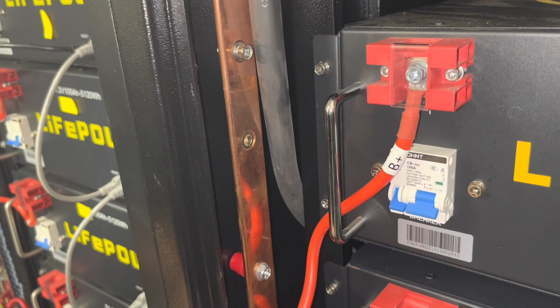All right, this is the older rack, and you see that lug. 100% surface area of this lug is on this bus bar, and that's really what you want for an electrical connection. So this design, in my mind, is far superior to that rivnut design that took out half the bus bar to put in a little rivnut of this for a boat this size.